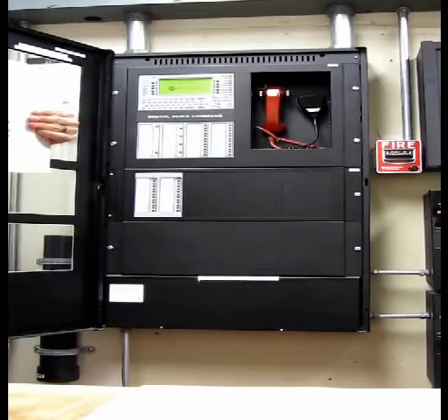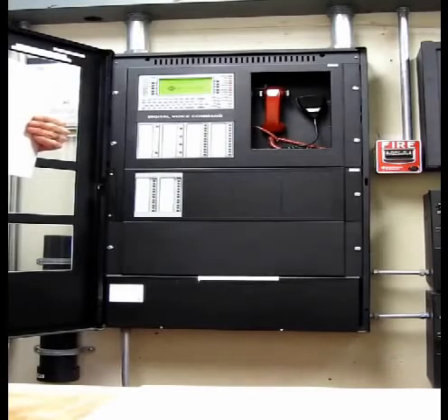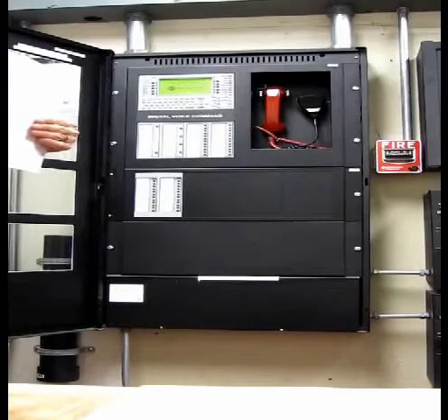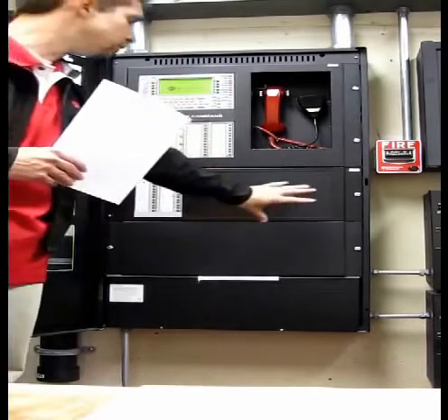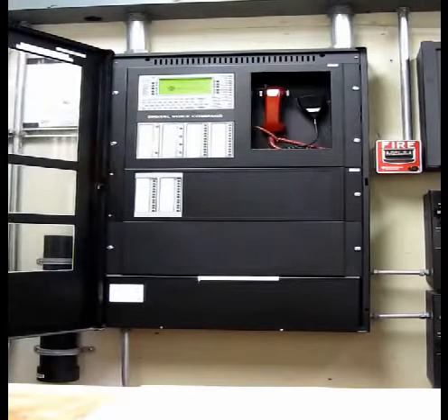And in the past, what we did is we'd investigate if it was a false alarm. We wouldn't contact the fire department. But now the fire department's going to be notified. Yeah, now they're automatically notified. And that's the next thing I was going to get into: now you have a dialer which is located behind this panel here. It's hooked up to 2 phone lines, and that's the whole point of putting the system on test.